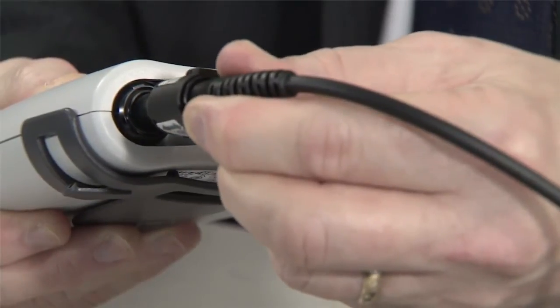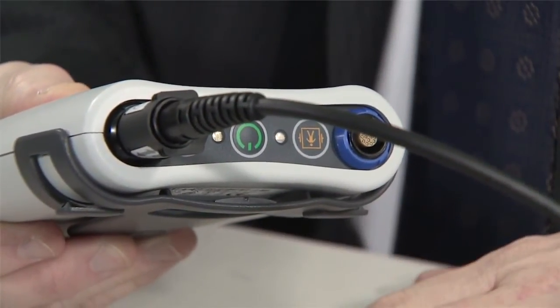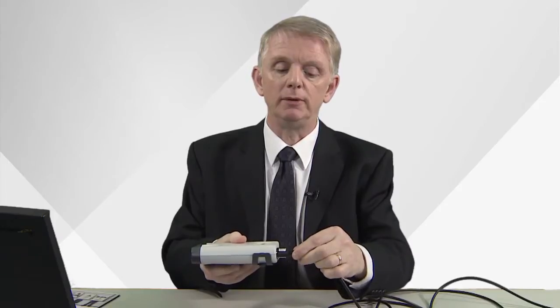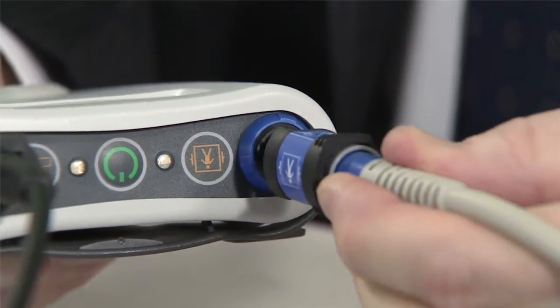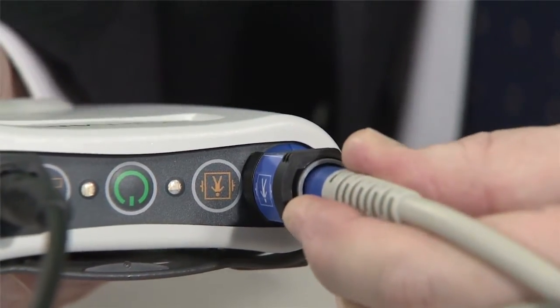Once you've prepared your patient, taking an ECG is really simple. To do this, connect the black USB cable to the black port on the top of the ECG. Now this can be done if the black arrow is on the top of the cable and the collar on the inside of the cable points inwards. It goes into the port like that. The same is true of the patient cable. This time there's a white arrow on top of the cable and again the collar on the inside of the cable points inwards. Those cables won't fit to the ECG any other way.